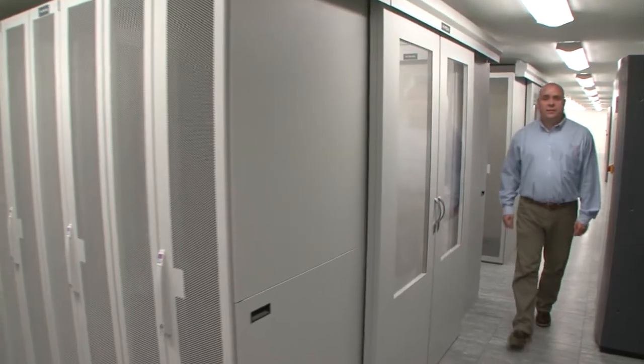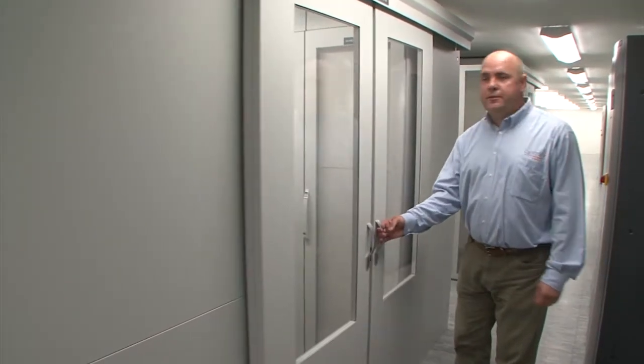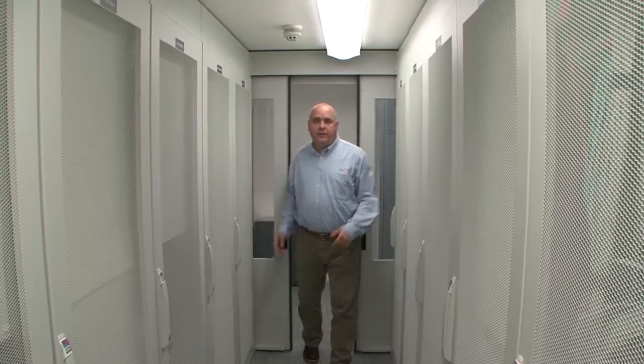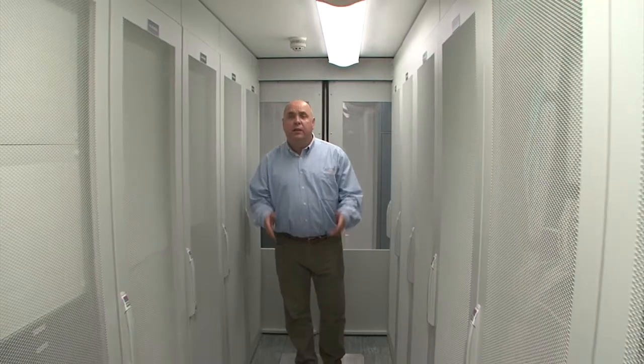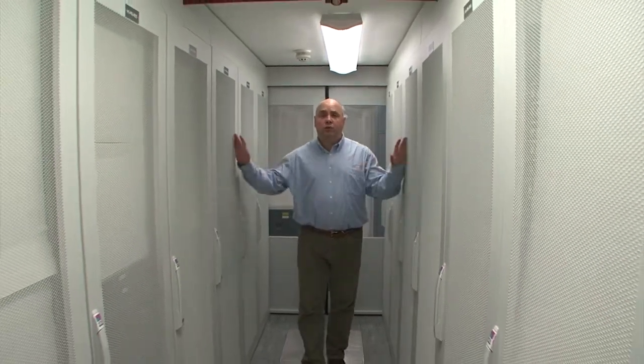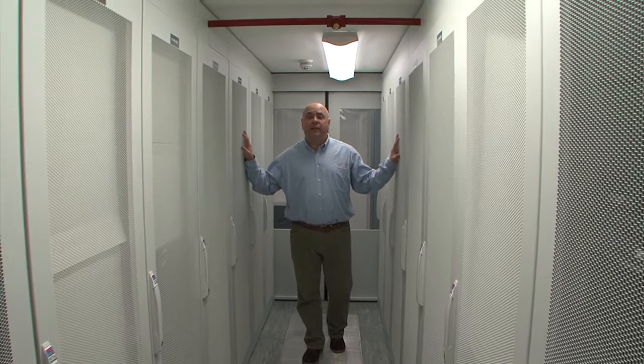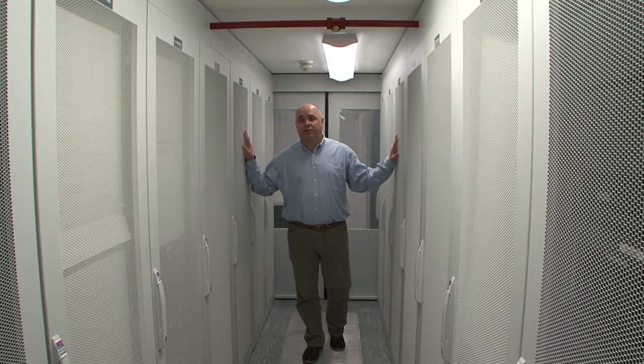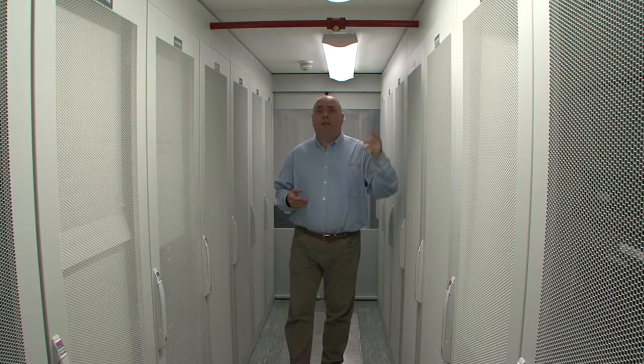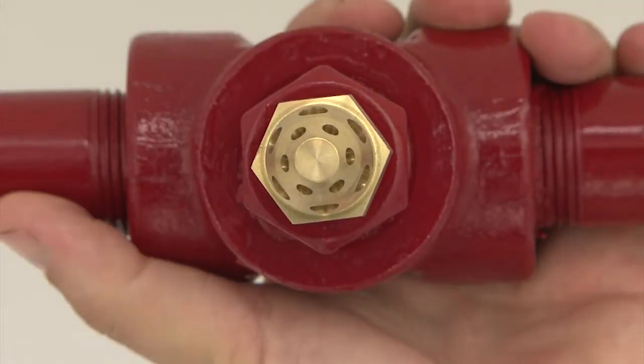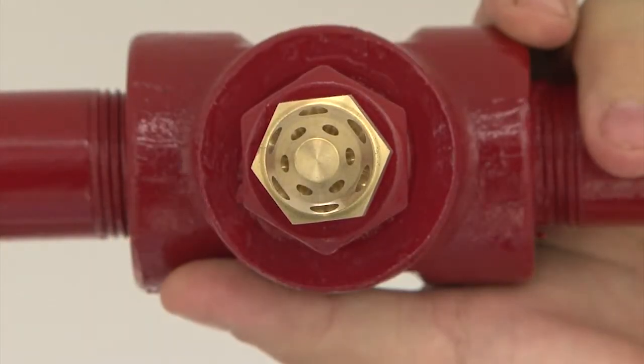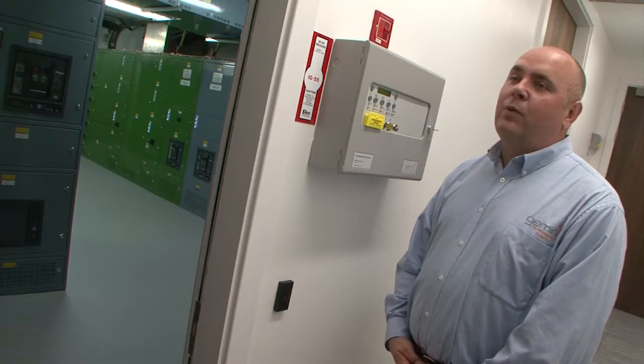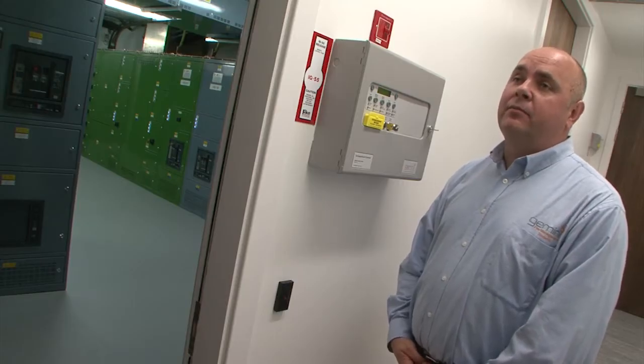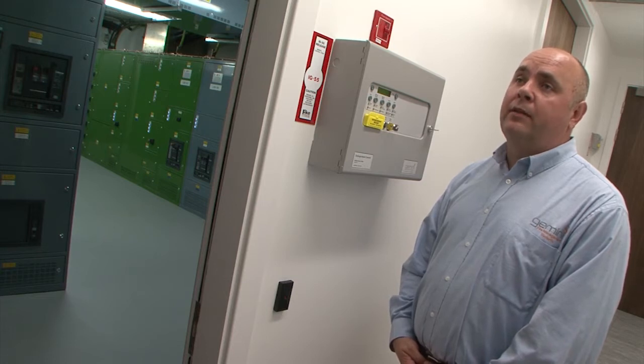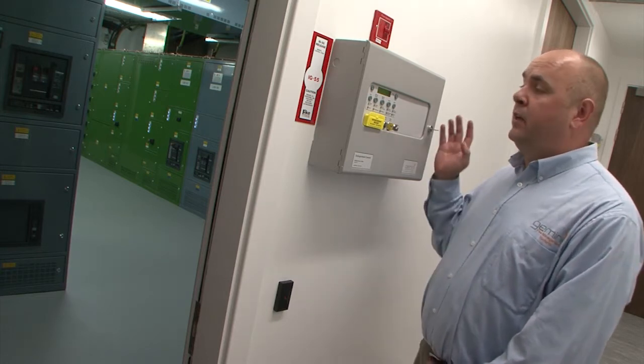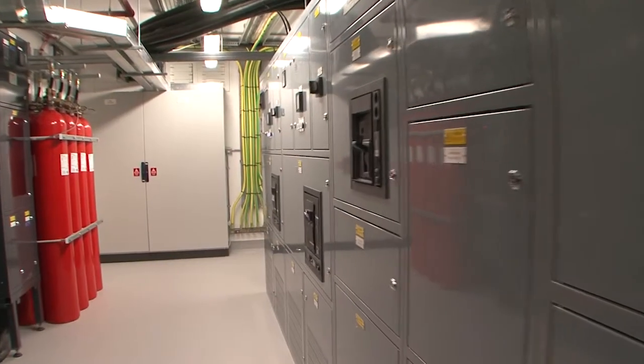At this data centre, cold aisle containment is employed. This means cold air is forced via the grills into the cold aisle, then drawn across the servers via the cabinets, and the heat is rejected into the hot aisles. Due to this, it was necessary to install a number of additional detectors and nozzles to provide adequate cover across the hall. As well as providing a selector valve system to protect the main data halls, a number of standalone systems were installed to protect critical areas, such as this system installed to protect the LV switch room.